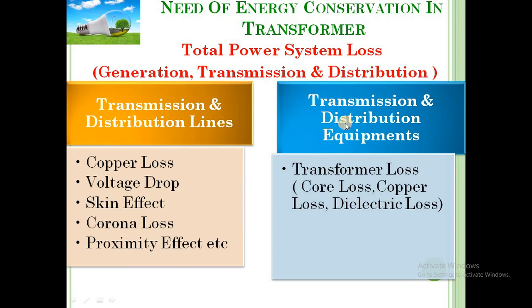Next, transmission and distribution equipment. Here the main equipment is the transformer, hence I have taken transformer loss, which includes core loss, that is transformer core loss, and the core loss is again divided into two parts: eddy current loss and hysteresis loss. Next is copper loss, which occurs in the winding. Dielectric loss occurs due to the insulation.